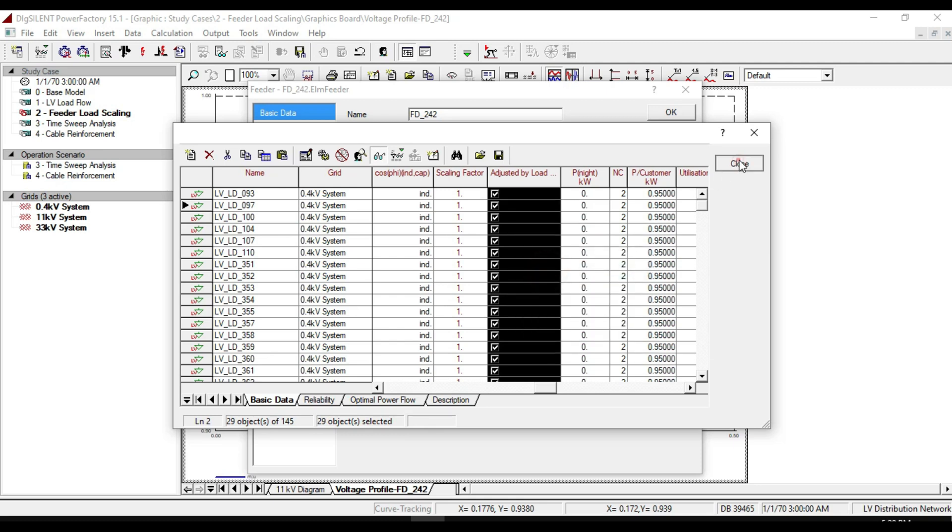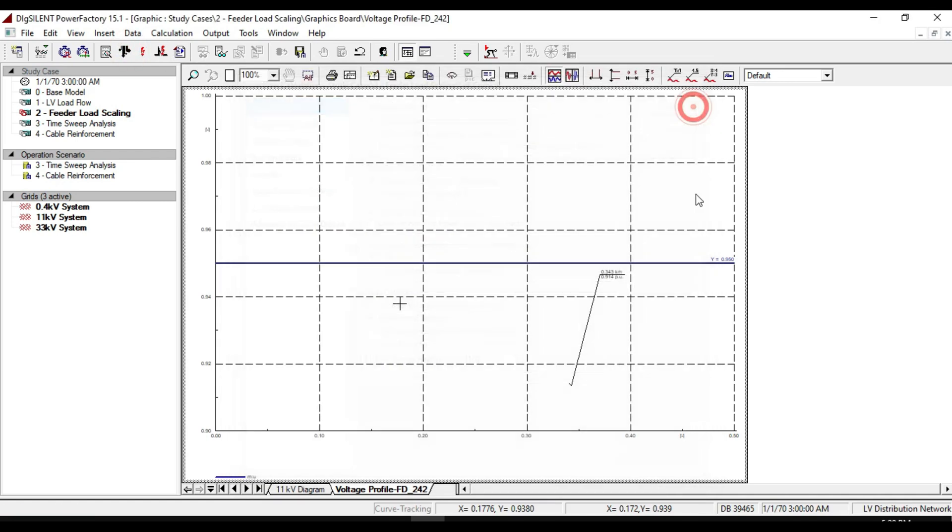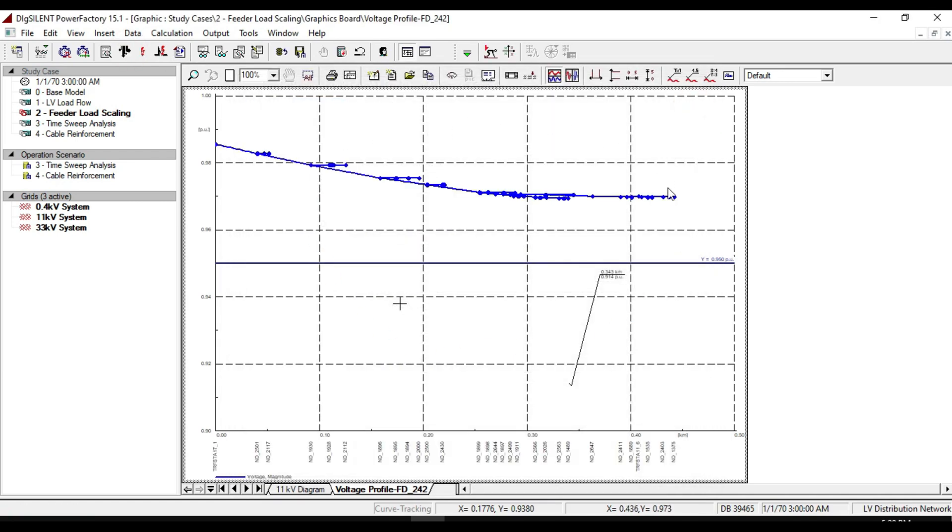If we take the load flow calculation, we will notice that the profile voltages are changing and all of them are above 95%, and the voltage drop on the feeder is substantially reduced.